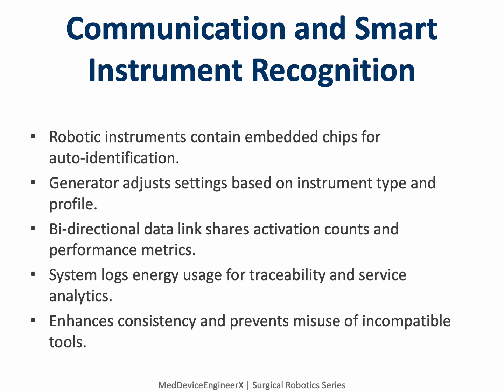Communication is intelligence that makes energy delivery precise. Each robotic instrument includes a small chip containing its identification data, type, energy mode compatibility, and usage limits. When connected, the generator reads this data instantly and configures its output accordingly. During operation, the system tracks activation time, delivered energy, and impedance trends, sending the data back to the control tower for logging.